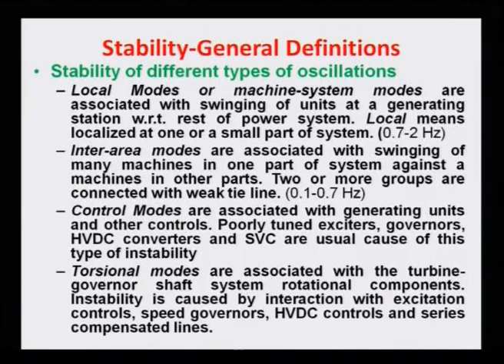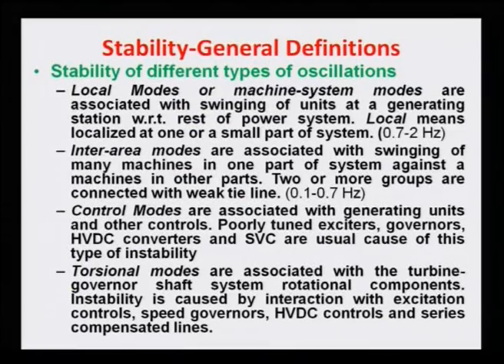The fourth category is the torsional modes of oscillation, and this is associated with the turbine-generator shaft system rotational components. The instability is caused by the interaction of excitation control, speed governors, HVDC controls and the series compensated lines. These torsional modes of oscillation are basically related to mechanical and electrical interactions. Our alternator is coupled with the various turbines on the same shaft, and some torsional modes of oscillation are observed which are less than 50 hertz. So these four types of oscillations are observed if you analyze your system with linearized differential equations.